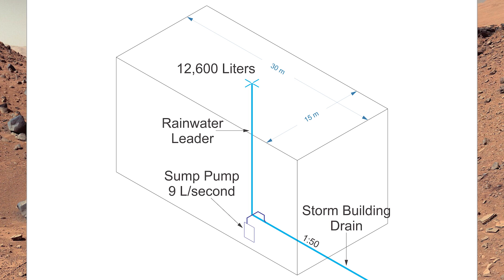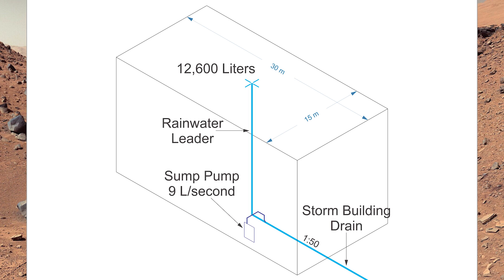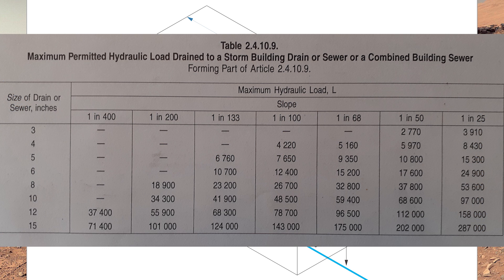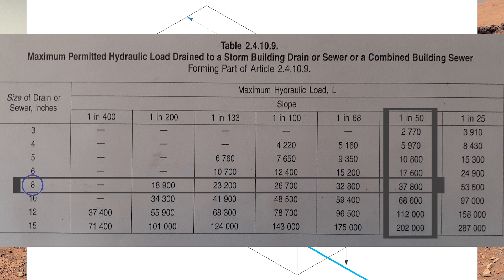The rainwater leader turns the corner and becomes the storm building drain. However, we also have a sump pump. In this example we're keeping things simple — that sump pump is rated at 9 liters per second. So we take 9 liters per second times 900, which equals 8,100 liters that the sump pump is going to dump into the storm building drain. So 12,600 liters plus 8,100 liters equals 20,700 liters. Looking at table 24109, going down the 1 in 50 column to 37,800 liters — we need to be 8 inches.